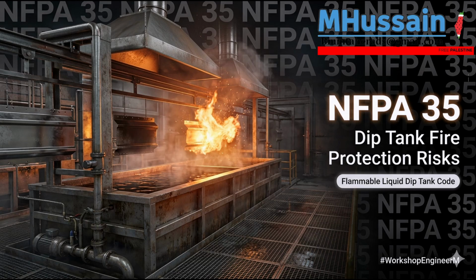We have engineered the ultimate building. The ventilation is meticulously sweeping the heavy vapors off the floor. The pipes are ductile steel, not brittle cast iron. The vessels are grounded to a strict 25-ohm resistance. The nitrocellulose is wetted down and protected by a hurricane of sprinkler water. It's all there. But all of this flawless engineering is completely, utterly useless if the humans running the plant make a procedural mistake. Welcome to the failsafe: management, fire protection, and maintenance.